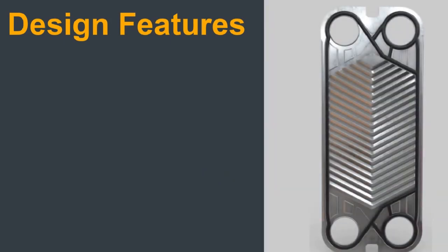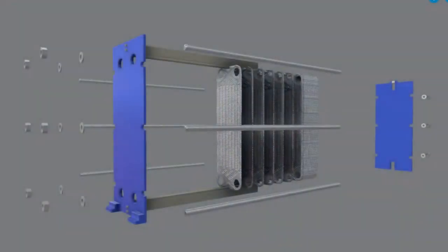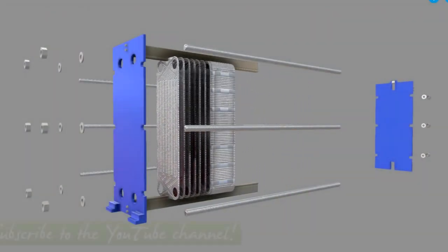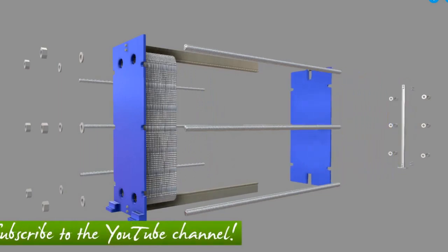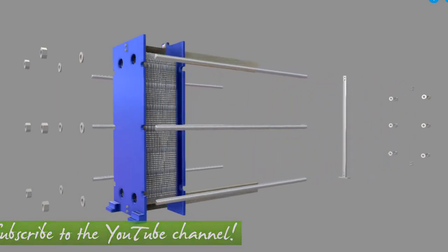But what makes plate heat exchangers so efficient compared to other types of heat exchanger, such as the shell and tube type? Let's look into some of the plate heat exchangers' design features. The plates themselves are the main reason plate heat exchangers are so efficient. This plate may appear simple, but it is actually full of interesting engineering design features. For example, when the plates are compressed together to form a plate stack, the gap between each of the plates is very small, which ensures good thermal contact between the two flowing mediums.